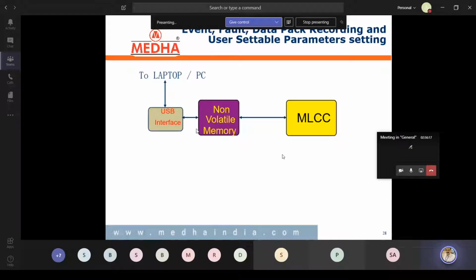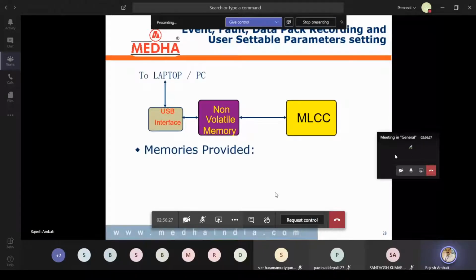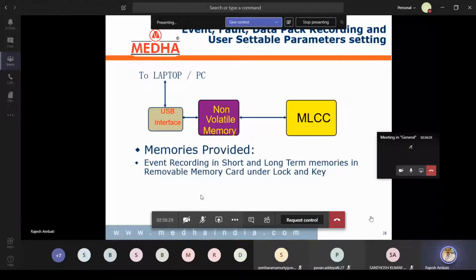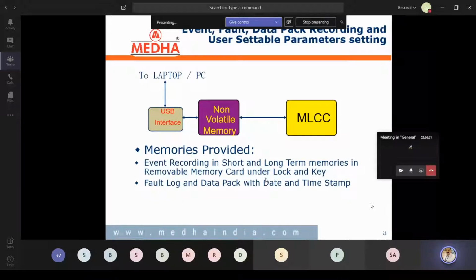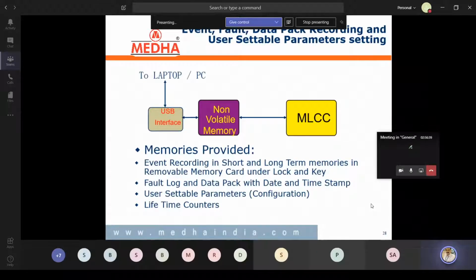And here there is a USB interface on the front fascia. We can retrieve the data by using a pen drive or any USB cable. Inside this, event recorder, short-term and long-term memories are there. Fault data pack is there with date and time stamp, user settable configuration parameters, lifetime counters, LTC. All this data will be recorded inside the flash memory, that is 128 MB.